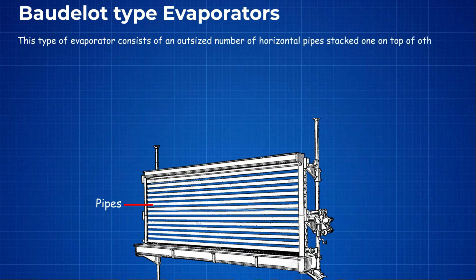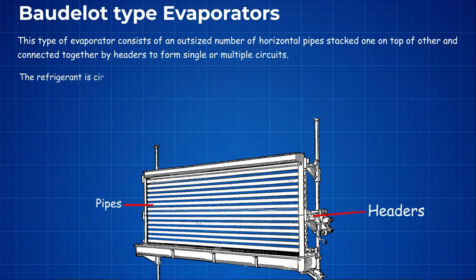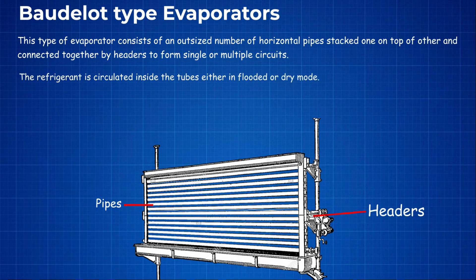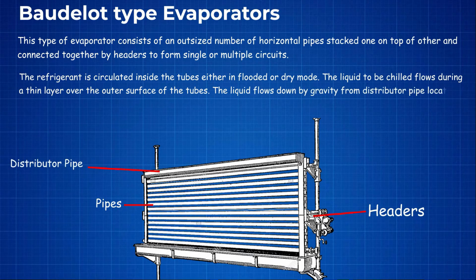The horizontal pipes are connected together by headers to form single or multiple circuits. The refrigerant is circulated inside the tubes either in flooded or dry mode. The liquid to be chilled flows through a thin layer over the outer surface of the tubes, flowing down by gravity from the distributor pipe located on top of the horizontal tubes.